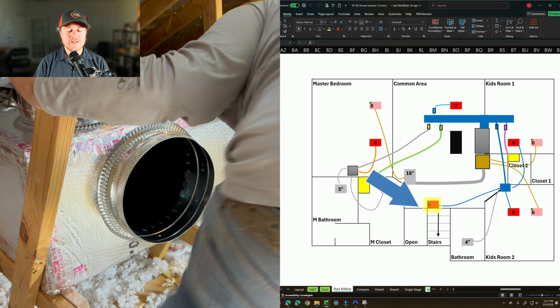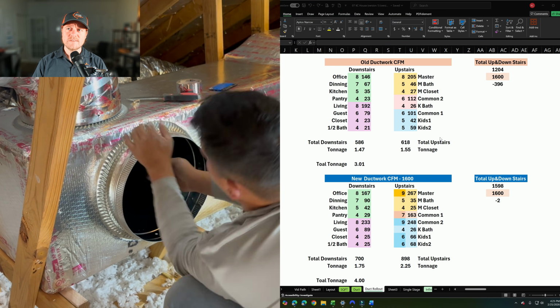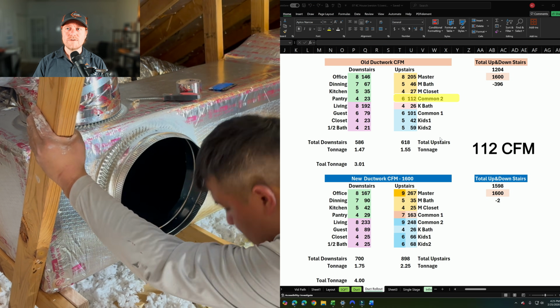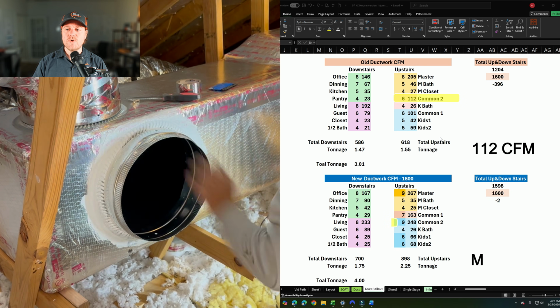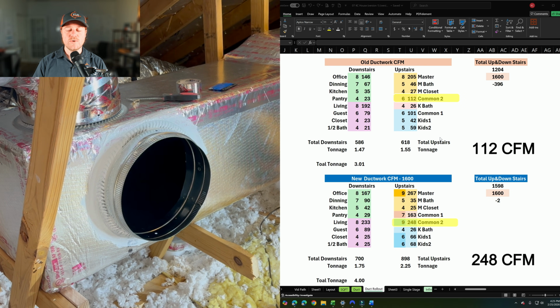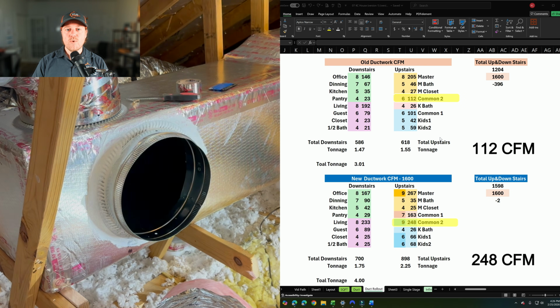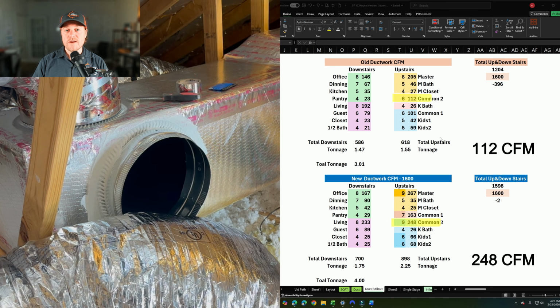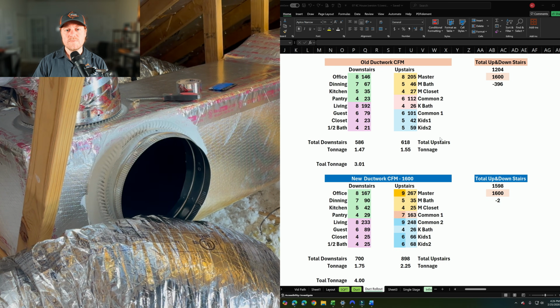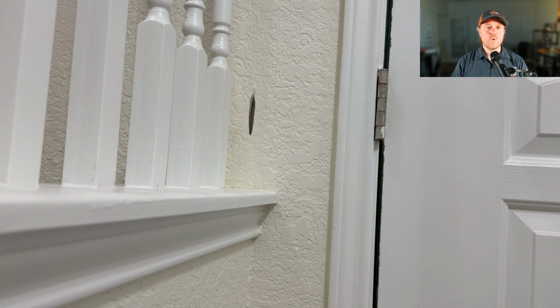Now let's pivot and look at the upstairs vent above the stairwell to see what it's doing. You can see that we used to have a 6-inch duct that was supplying 112 CFM. We changed that to a 9-inch duct that is now supplying 248 CFM. So we ended up more than doubling the airflow over the stairs. And that means a chunk of that is going to make its way downstairs. I'll show you a quick example of this.